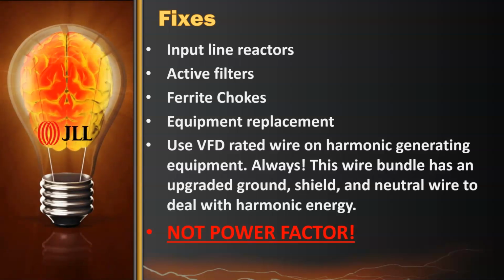And they are insulated, so they just clamp. It's a three-phase device. You clamp one on each conductor, and away you go. Depending on the amount of harmonic, you might have to put a couple on there. I've never had to put 3 on, but if it's a large chiller, you might have to put a couple of ferrite chokes on there. The big ones cost about $150 a pop. You can buy lots of the smaller ones for $100 a pop.